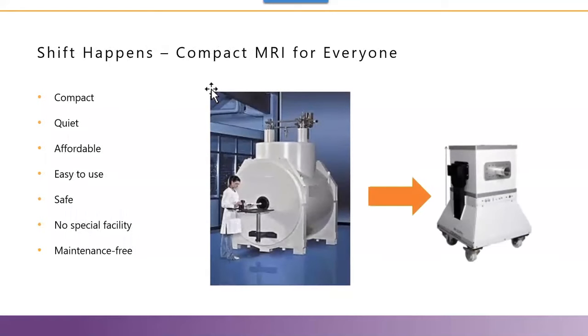The benefits of the M-series compact MRI system include quiet operation, low cost, no shielding required, normal lab safety, one-day system setup, maintenance-free design, no special staffing requirement, negligible running cost, and it can be placed anywhere in the facility — next to other imaging modalities, behind the barrier, benchtop, and easily moved to a different location.